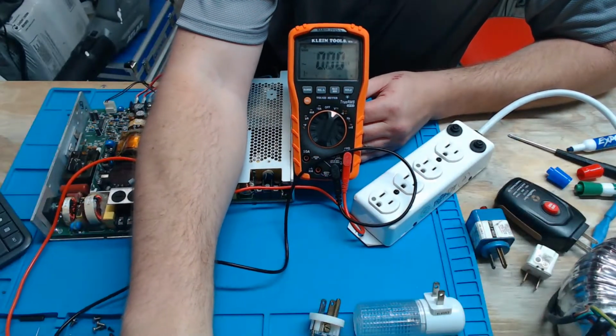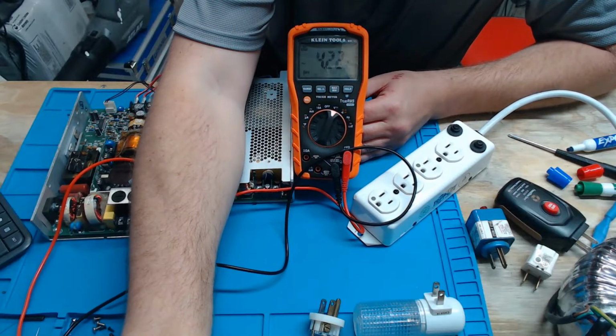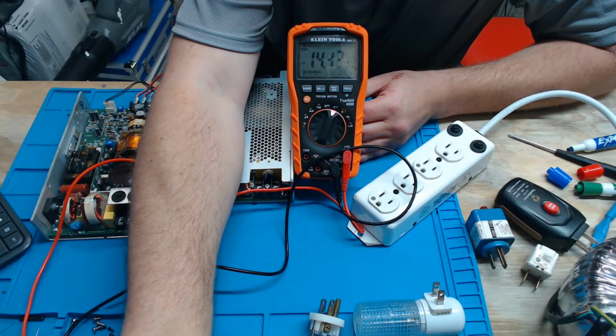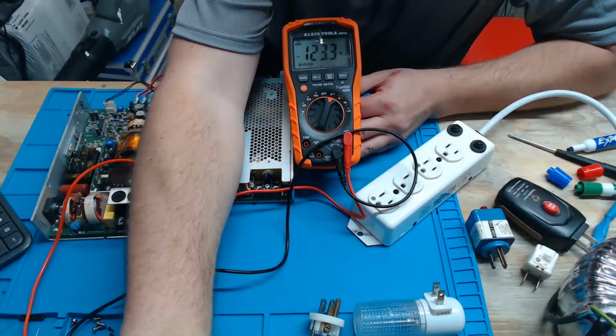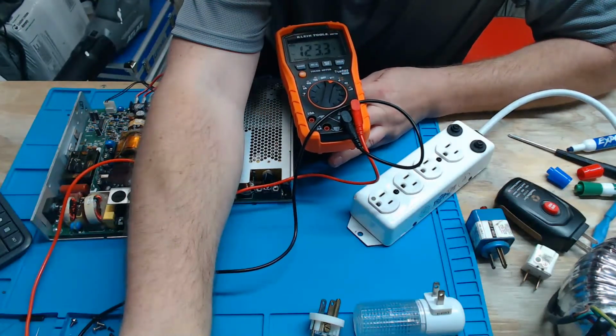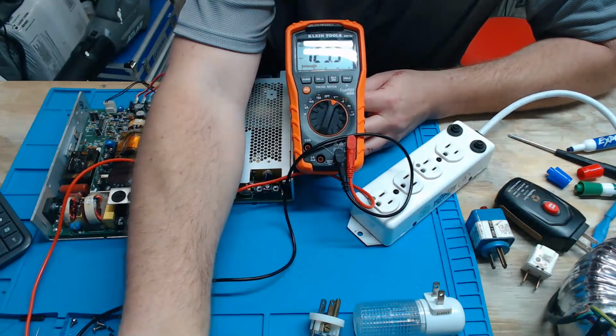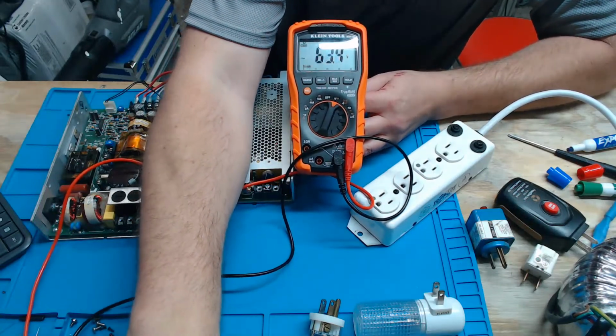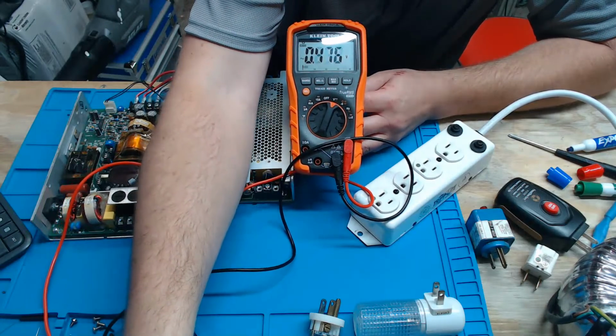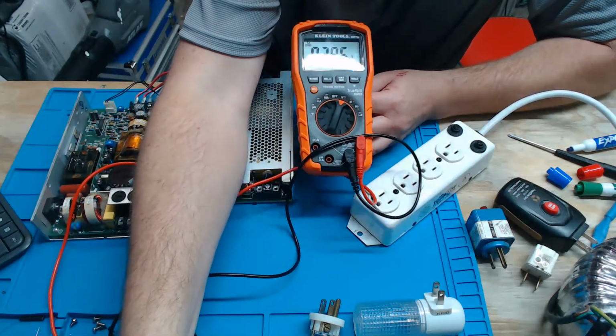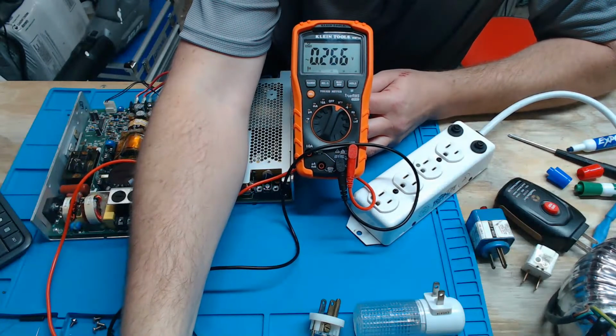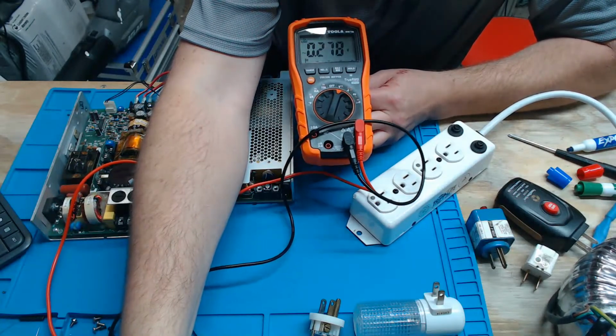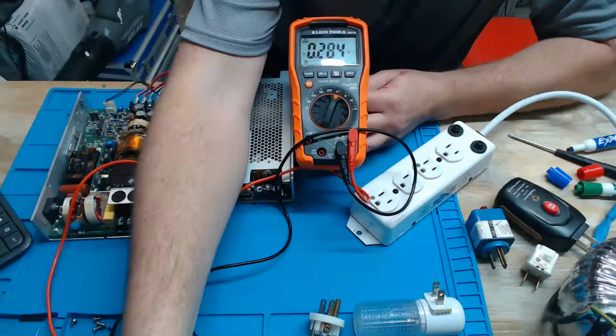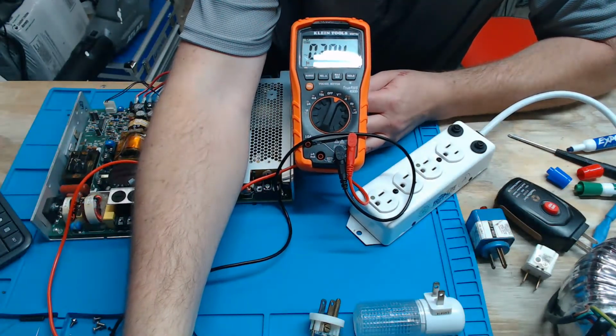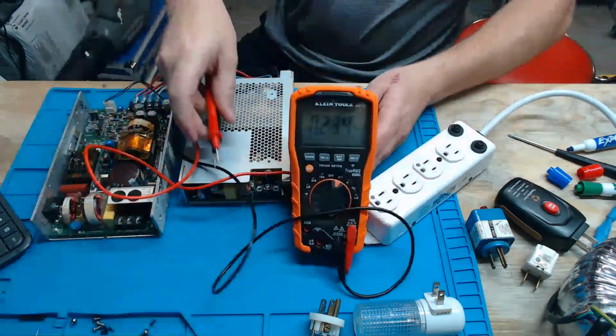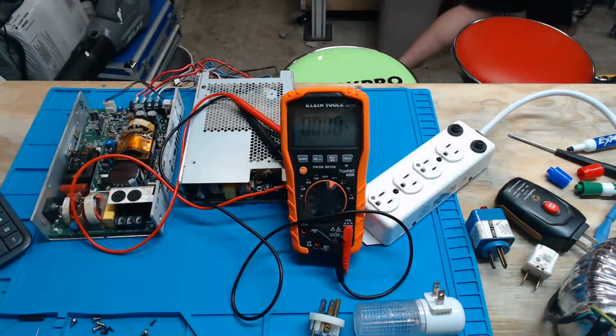So let's say I go from the line side to ground. What do we see? I see 123 volts. Line to ground. That's right, guys. Neutral and ground on a traditional electrical outlet, like right here, you will have technically nothing, right? Technically nothing. I got what, 0.28 of a volt, something at best. So not very much at all.